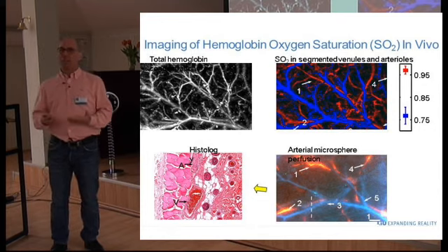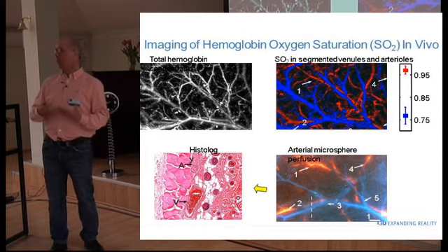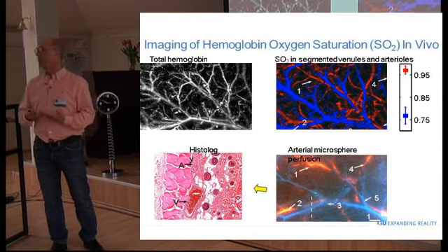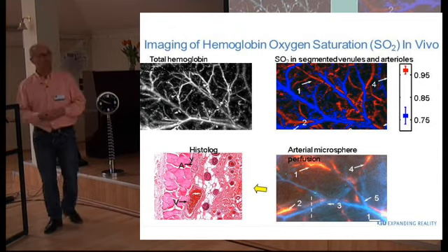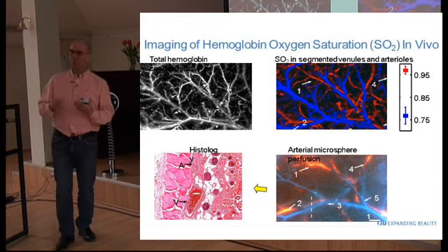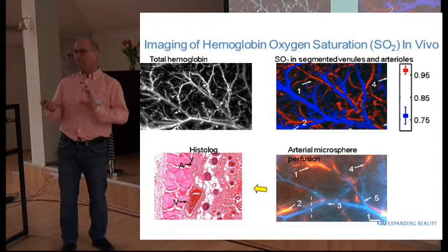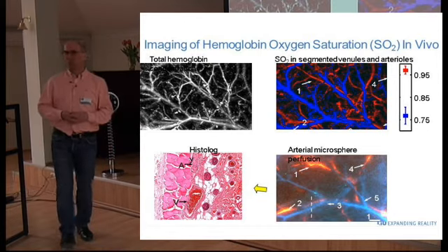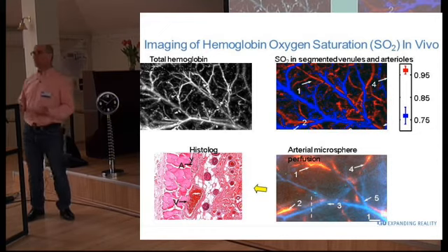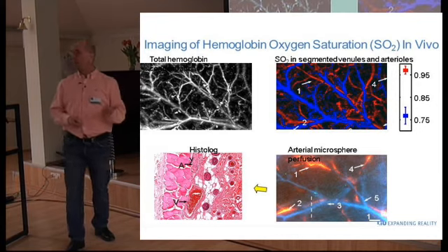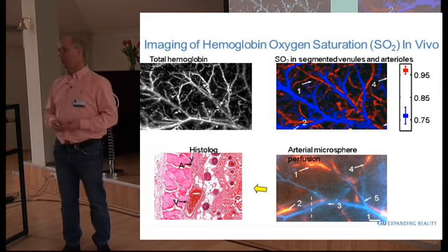But there are technologies able to go deeper into tissue, because I told you that diffuse optical tomography is hard to do because it gives you a very bad signal-to-noise ratio. That is, of course, photoacoustics. The trend is now going into more multimodal imaging, using different types or hybrid systems. And photoacoustics, I would say, is one of the first systems using hybrid. It consists of lasers and ultrasound.